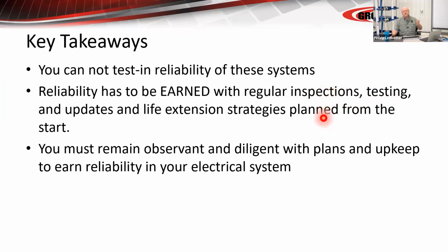An inspection to me is an audio test where you listen for insulation breakdown. It's oil testing in transformers. It's cable testing with PD detection. It's all these sorts of things that are inspections. Some of it's online, some of it's offline, but it's all very important. The actual testing is where you actually apply a potential or a current and look for a particular result to test the system and make sure it's going to perform as required.